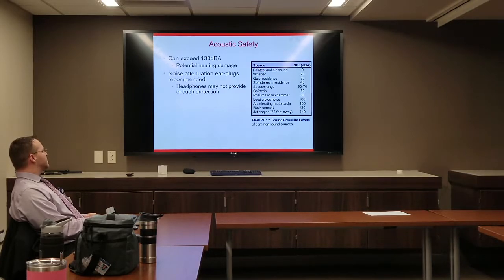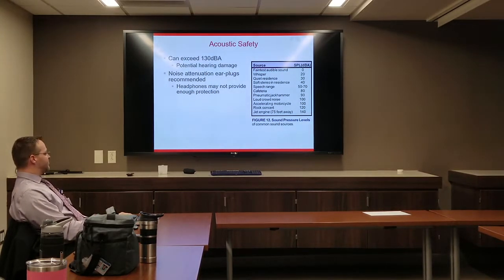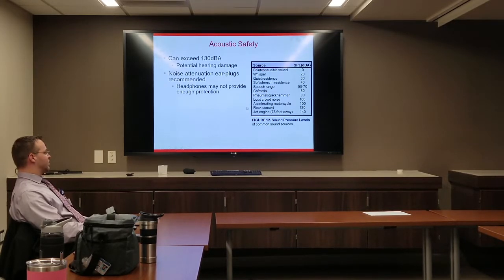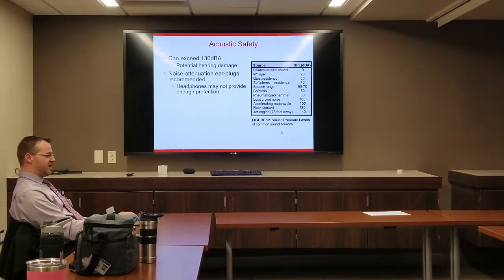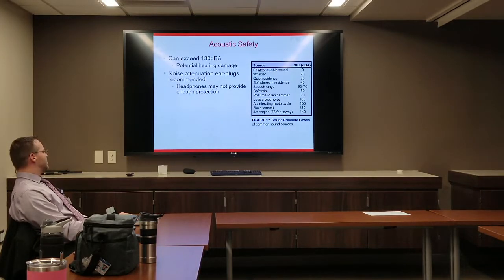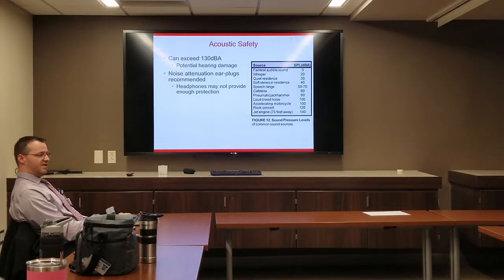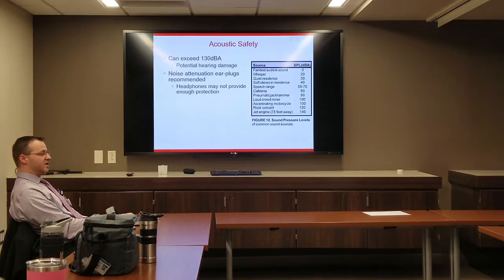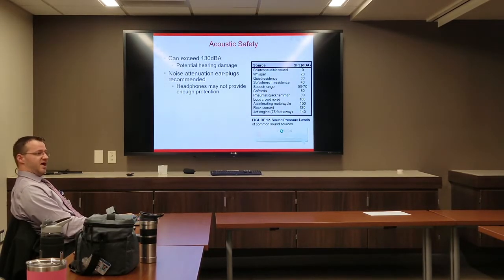For acoustic safety: most scanners nowadays will easily exceed 130 dBA, which can potentially lead to hearing damage — potentially louder than a rock concert or close to a jet engine at close range. Hearing protection is important. Noise-attenuating earplugs are recommended because headphones may not provide sufficient hearing protection. For example, on Siemens scanners, the headphones may only dissipate about 12-15 dB, while the scanner can reach 120-130 dBA — so headphones alone are generally not enough protection.